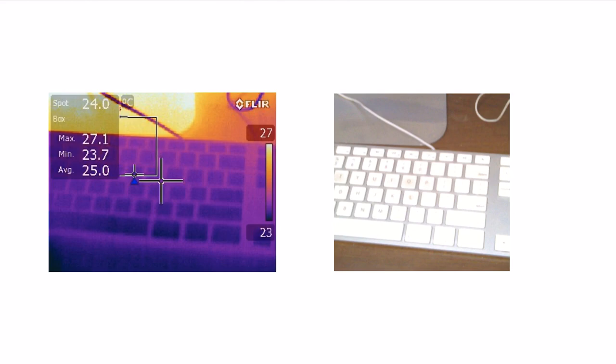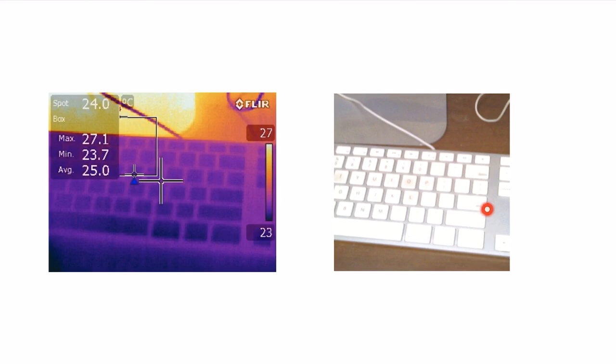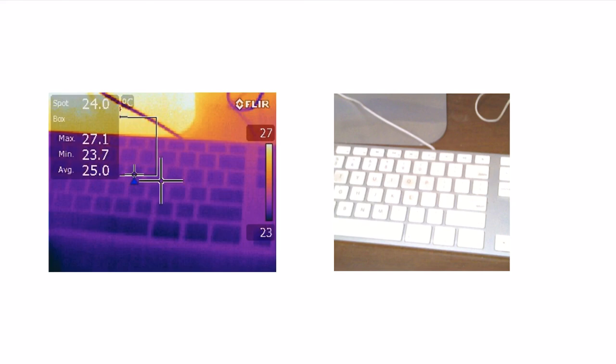Let's look at what that means in practice. Here's a picture of my keyboard and monitor stand. Here's the visual image taken at the same time by the camera, and here's the IR image. This is sitting on my desk, probably in thermal equilibrium such that the keyboard is all at the same temperature. What you see is that these white keys are reading at a higher temperature than this aluminum material behind it. That's because this shiny aluminum has a much lower emissivity, so it's indicating a noticeably lower temperature. That's not because the temperature is different—it's because the emissivity of this material and this material is different. We have to be cognizant of those differences when looking at that image.